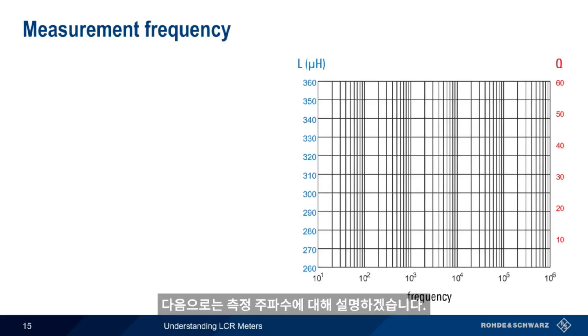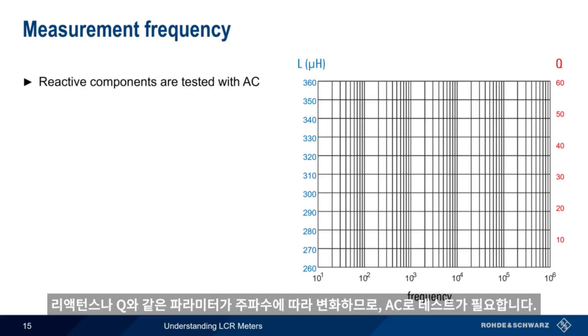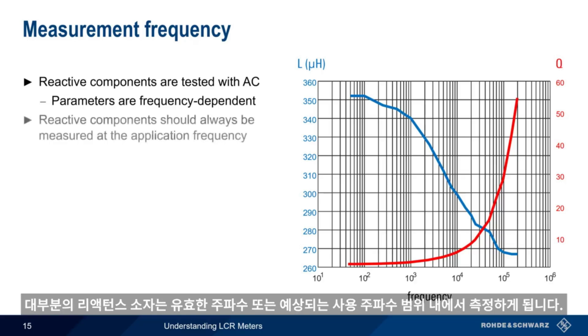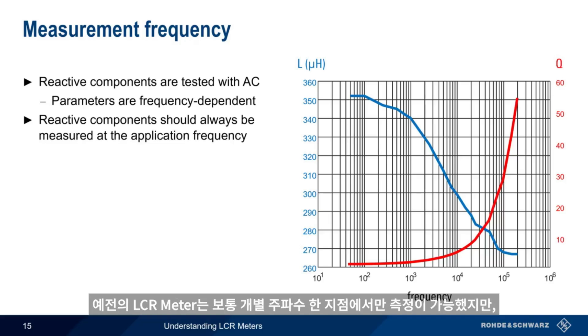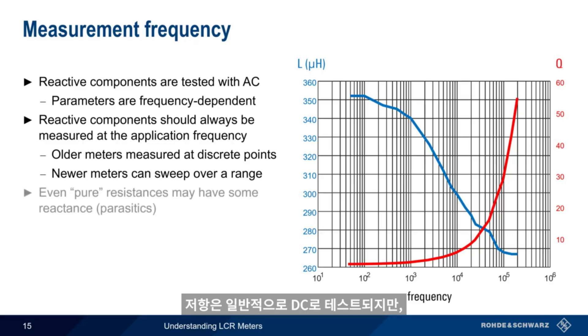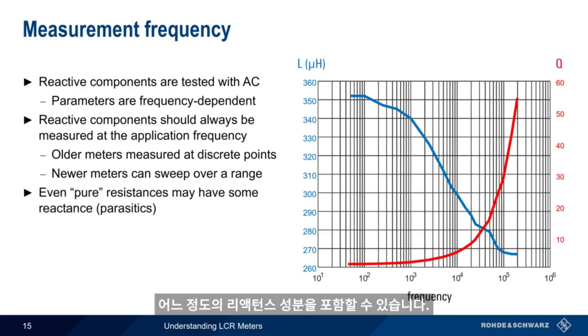Next, let's talk about measurement frequency. Reactive components such as capacitors and inductors are tested with alternating current, because their parameters — such as reactance and Q — are frequency dependent. In most cases, reactive components should be measured at the frequency of intended application, or across the expected application frequency range. Older LCR meters often only measured at discrete frequency points, but newer meters are able to measure by sweeping across the defined frequency range. Note that even pure resistances may contain some reactance when tested using AC at different frequencies.